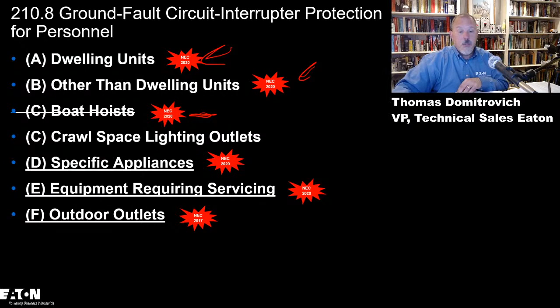In 90.3, 1 through 4, we already talked about that. We already said you've got to be mindful of 210.8, other than dwelling units and in dwelling units, because marinas - I could have a boat dock in a dwelling unit area, multifamily, single family dwelling units. I can have it in other than dwelling units. We moved boat hoists back to 555 because that's where it makes sense. So we still have the GFCI requirements, but we moved those back to 555.